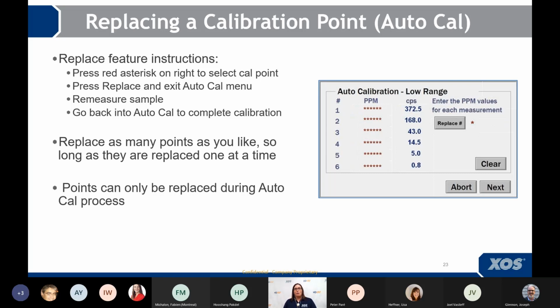Very simple. But what happens when you get a bad calibration point? Because you only have 6 spots for AutoCal. A lot of people aren't aware of the replace feature. The replace feature allows you to replace a point in the calibration. So when you replace the point, the next sample that you run, instead of going into position 1, will replace that calibration point number. Say, for example, calibration point 3. I didn't like that one. So I would go over to the right and touch that red asterisk, type in 3, and then touch replace. When you exit out of AutoCal, you then run that standard, and that point will go into spot 3 in this auto calibration queue.